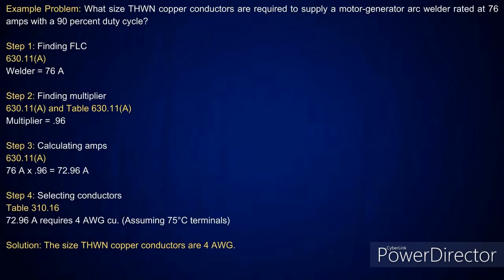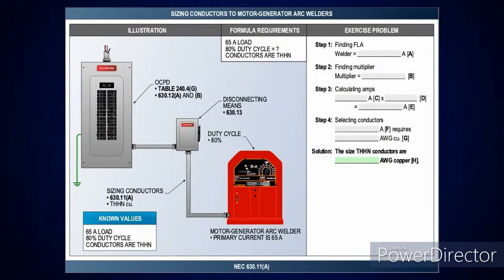All right. So we had a 0.96 multiplier. Take that times 76, gives me 72.96. The next size above that is 85 amps in the 75-degree C column, which will be a number 4 conductor. Okay. And there you go.